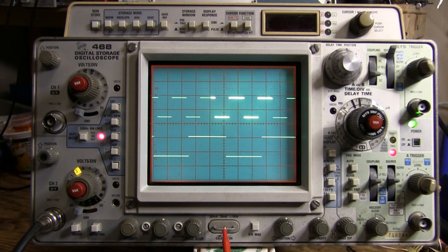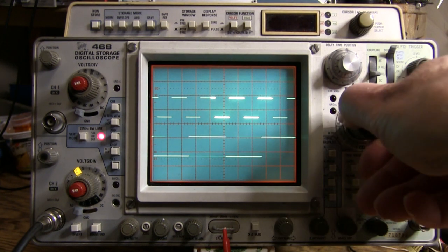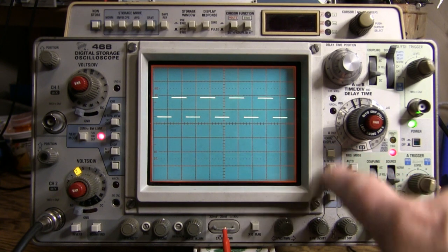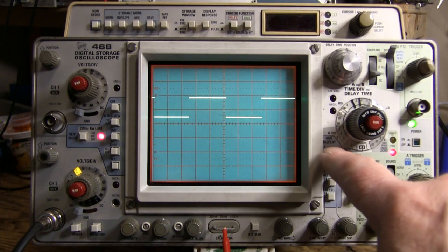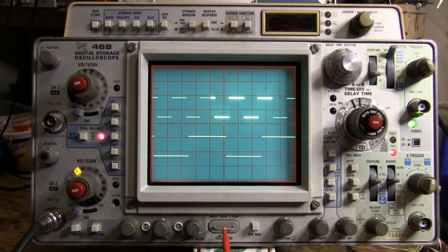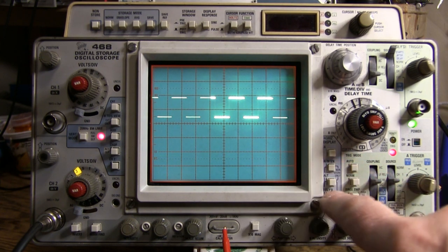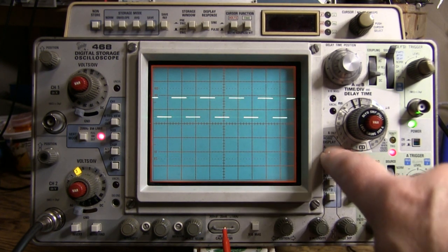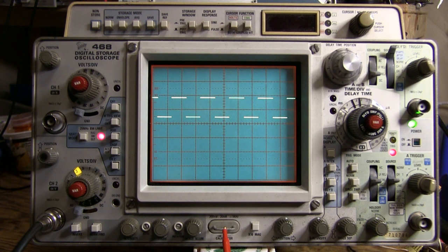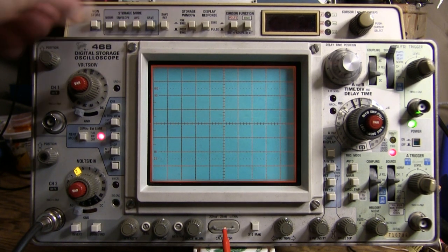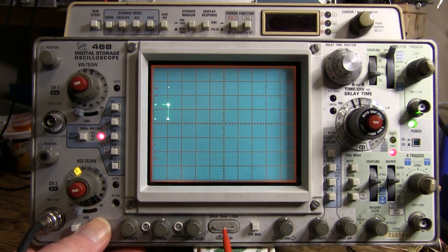In non-storage mode the A and B sweeps work normally but in storage mode if we go to storage mode, no sweep. If I do beam finder I see the dots move off screen so the beam is just off to the left, but in B mode, B only, the sweep works okay.